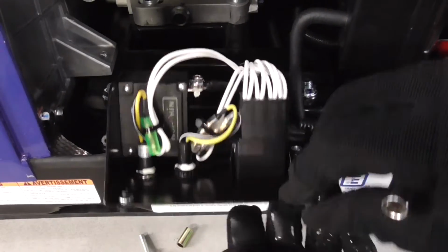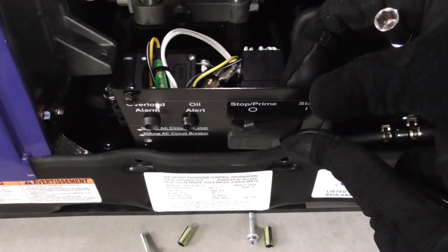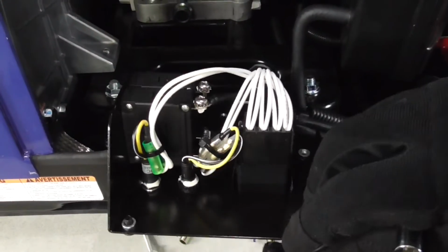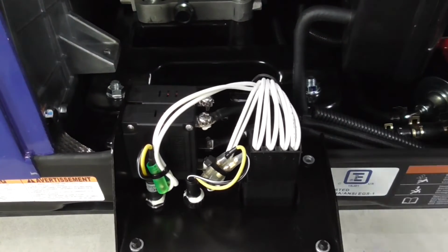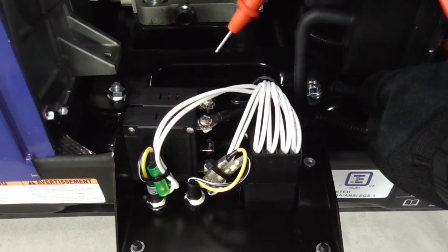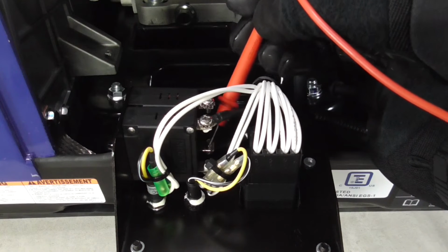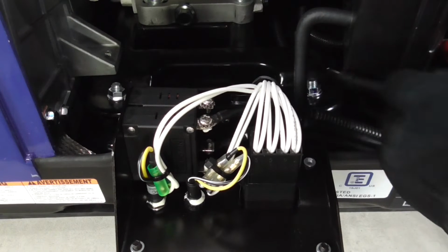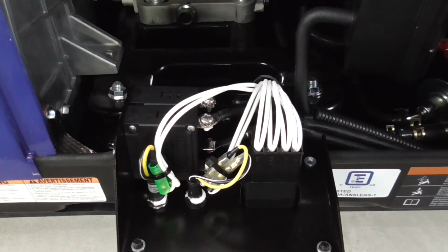With the control panel out and being careful not to touch anything metal, start the generator, then put your voltmeter probes on a ground plane for one probe, the other probe on the input of the breaker, which is towards the front of the control panel. Check both breakers. If you have voltage on the input of the breaker and not the output of the breaker, the breaker needs to be replaced. If you don't have voltage on the input of the breaker with the generator running, this needs more troubleshooting. Call our tech support line.